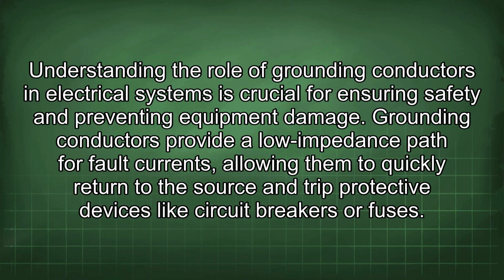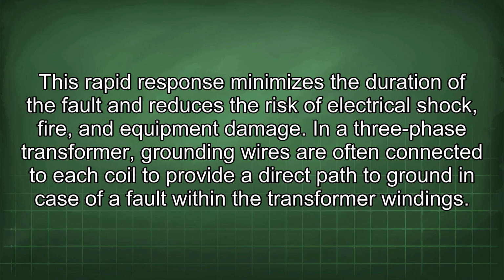Understanding the role of grounding conductors in electrical systems is crucial for ensuring safety and preventing equipment damage. Grounding conductors provide a low impedance path for fault currents, allowing them to quickly return to the source and trip protective devices like circuit breakers or fuses. This rapid response minimizes the duration of the fault and reduces the risk of electrical shock, fire, and equipment damage.